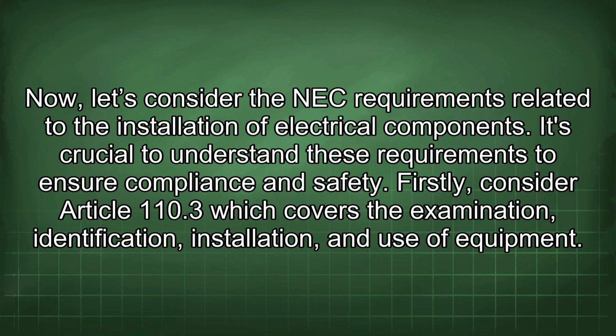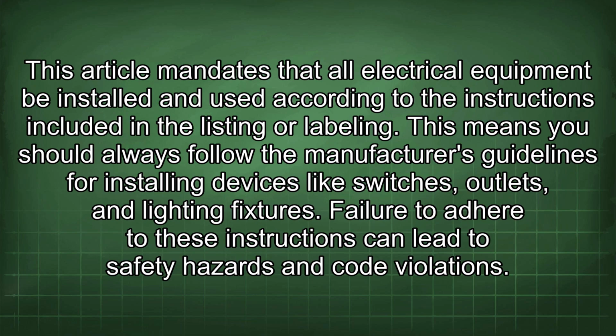Firstly, consider Article 110.3, which covers the examination, identification, installation, and use of equipment. This article mandates that all electrical equipment be installed and used according to the instructions included in the listing or labeling. This means you should always follow the manufacturer's guidelines for installing devices like switches, outlets, and lighting fixtures. Failure to adhere to these instructions can lead to safety hazards and code violations.